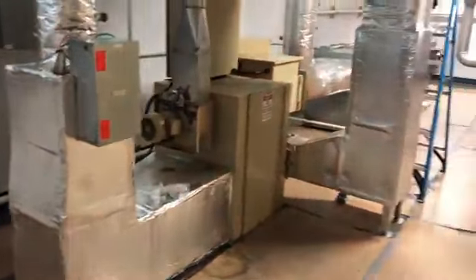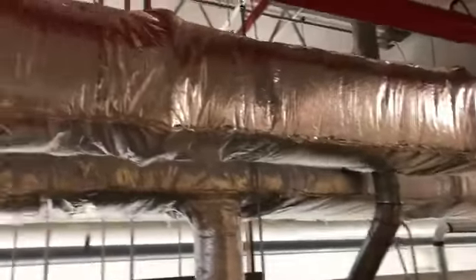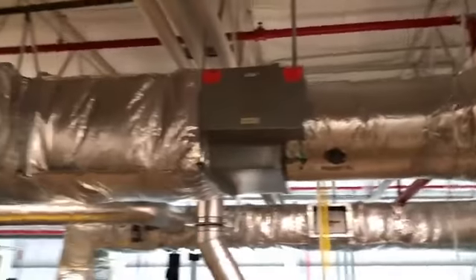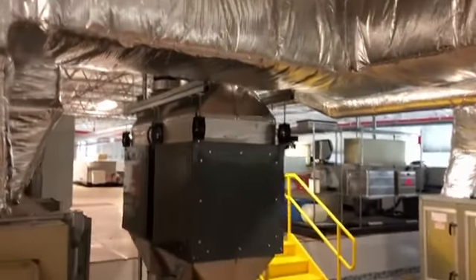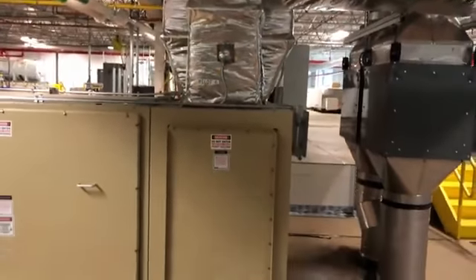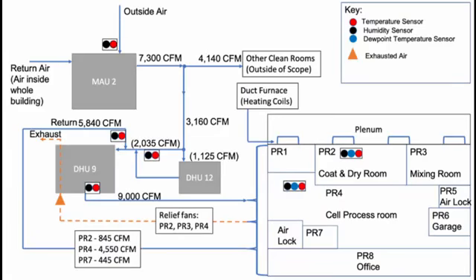Once the air passes through the makeup air unit, the air can either go through the small dehumidification unit DHU12, or if dehumidification pre-treatment is not necessary, it can be mixed with the room return air and go directly to the main dehumidification unit DHU9. The air will then go into a plenum, which supplies the air to the pilot DCR through vent fans. This air is then vented out and recirculated back to be mixed with the intake air before DHU9. Also, from the schematic, you can see the locations of the sensors that are currently in the system, which include the temperature sensor, the humidity sensor, and the dew point sensors.